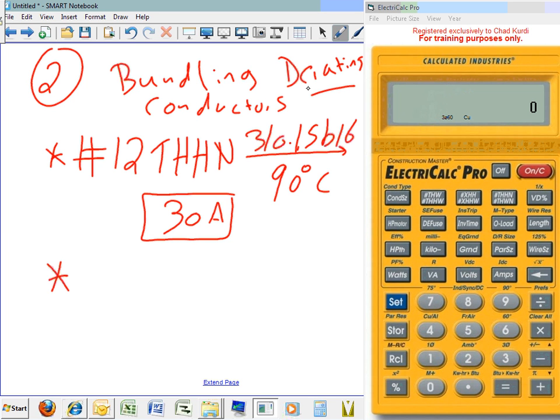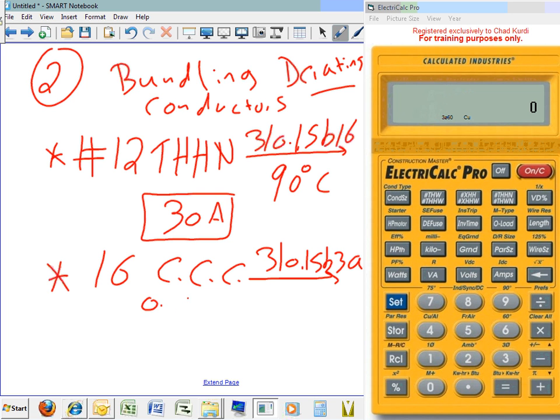Why do I have to count the neutral? Because I'm feeding lights, most likely, or even receptacles that feed laptops and everything else. So the worst scenario is the neutral has to be counted. Cool, everybody knows why we're counting the neutral. So these 16 conductors are actually 16 current-carrying conductors, all of them, the neutral and the hot, because of the harmonics. If you take this one to 310.15, which table is that? 15, B3A, B3 and A. What is the derating factor for this? 0.5, 50%. My derating factor is 0.5.